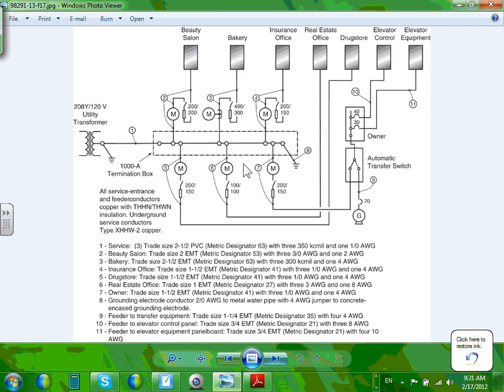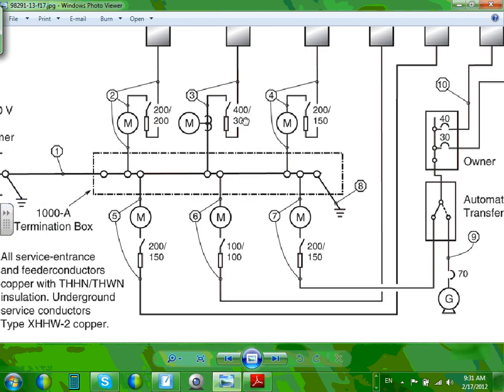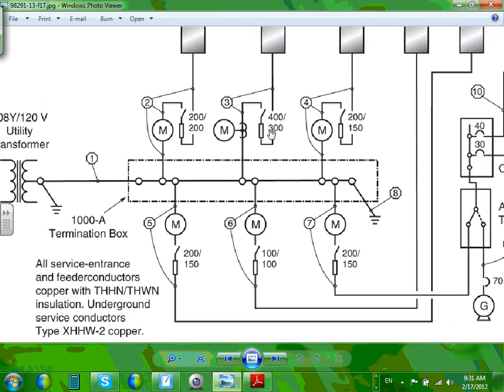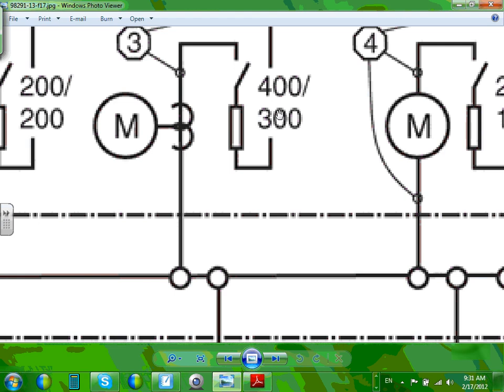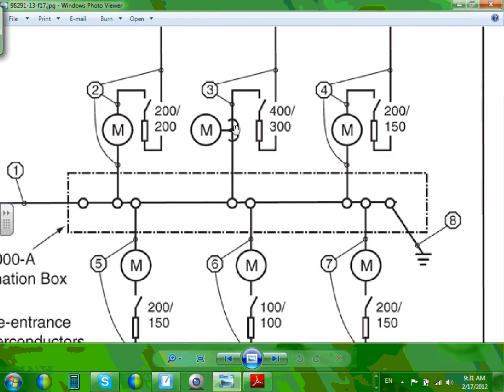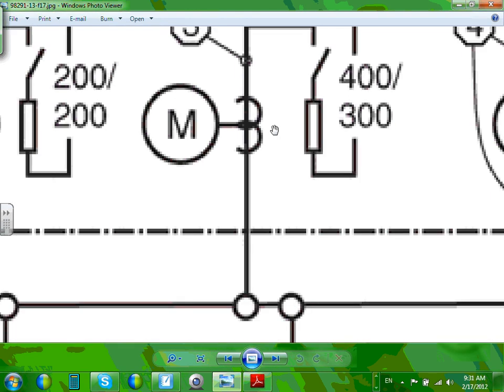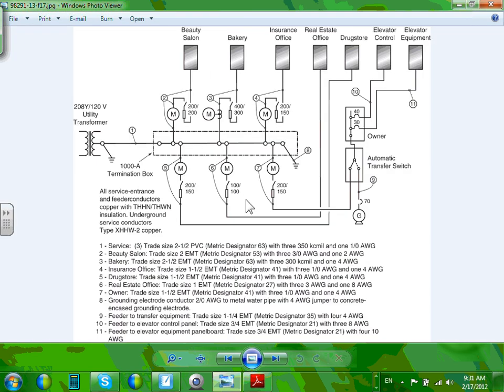So here's the one-line diagram, guys, for this system. Do you see where the CT cabinet is needed? Can you guys see where it says 400 amp disconnect and 300 amp fuse? That's why, right here. That's why we have a CT cabinet here. And can you see where they describe the CT cabinet? Can you guys see that little symbol with meter? That's a CT cabinet, or the CTs. Everything else will be measured directly.